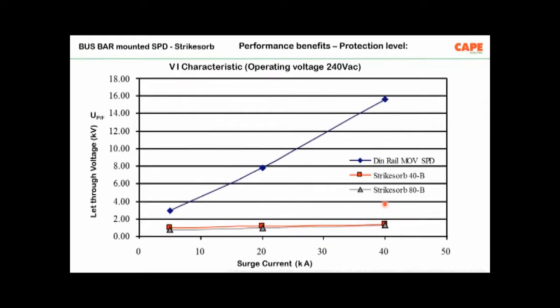I'm just showing you a test result of an SPD. The first one, the blue line, is the effective voltage protection level of a DIN rail mounted SPD, and the other ones, the black and the red, are the effective protection level of a bus bar mounted SPD.